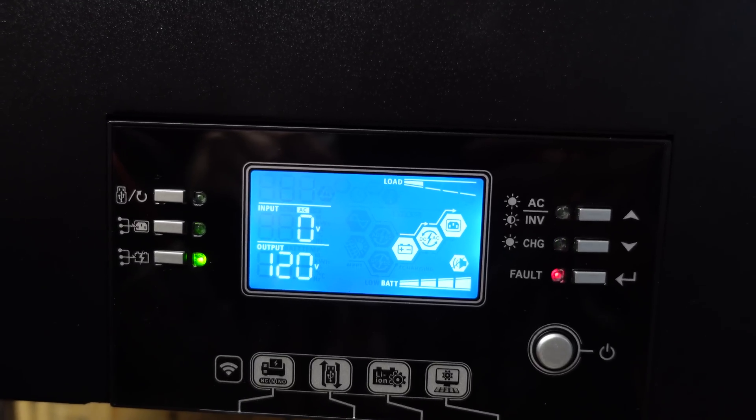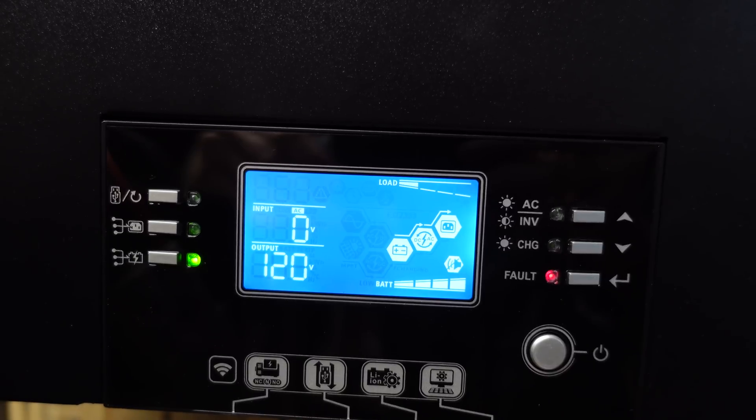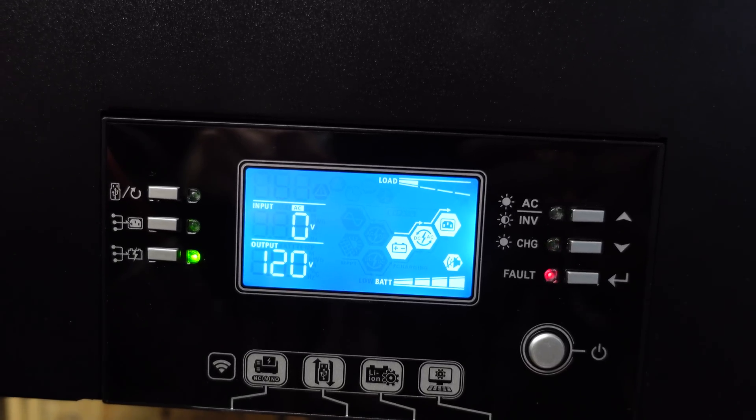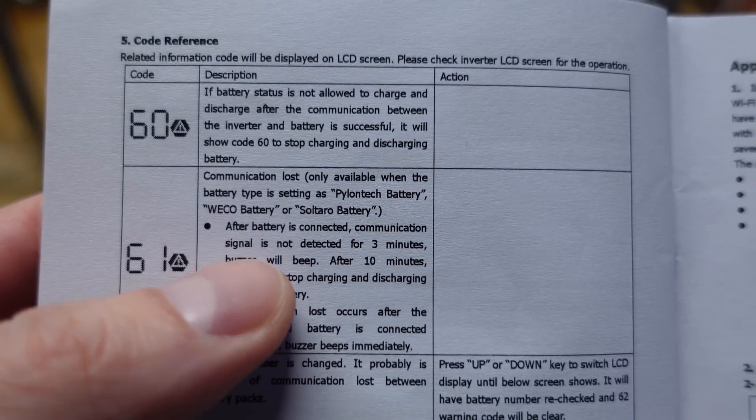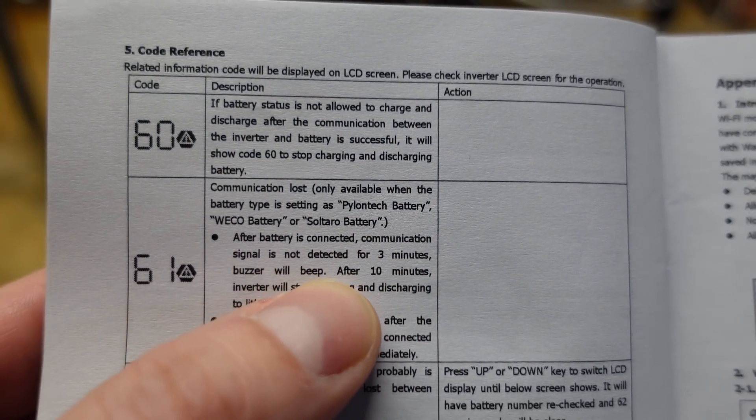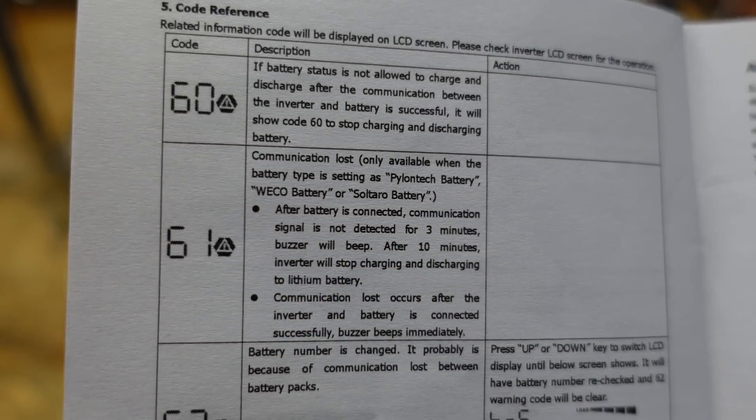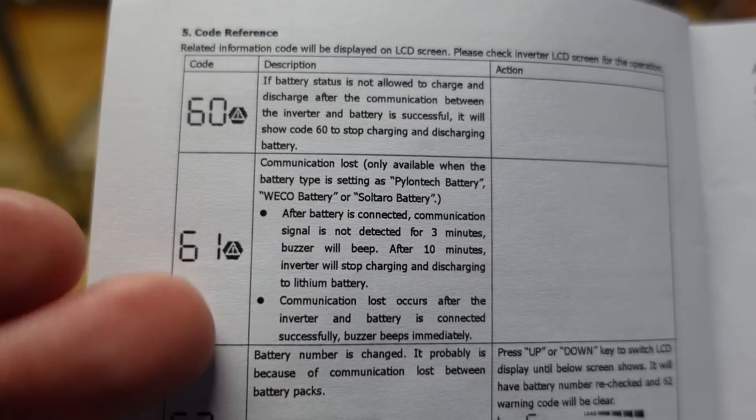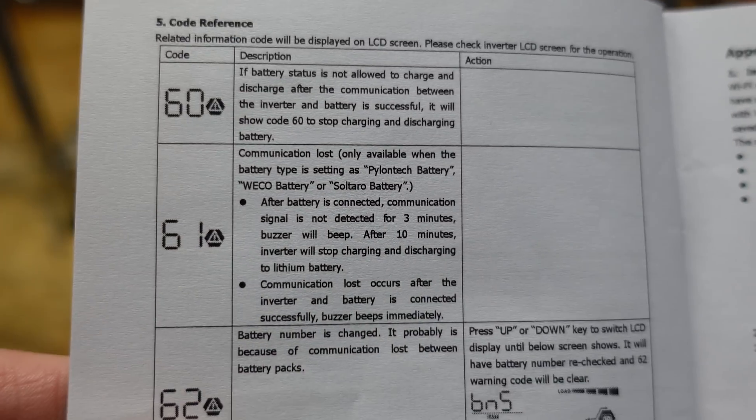Now, after a few minutes, you can see we have code number 61, a fault state flashing on the inverter. Back to the inverter manual. Code number 61 occurs when communication signal is not detected for three minutes. After 10 minutes, the inverter shut down, and the inverter does indeed shut down if I leave it wait for that 10 minute period.